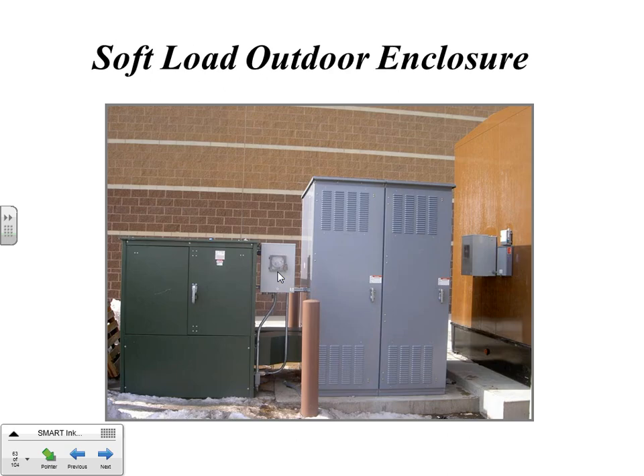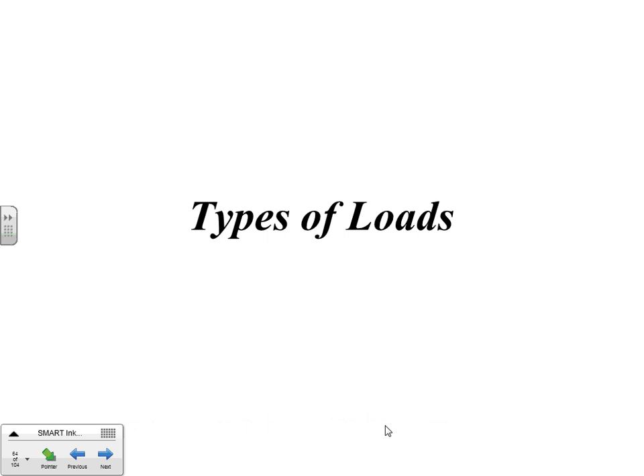This is what it would look like sitting outside of a building. If you remember that super target picture before, it's the same one. The generator has now been set here, and like Chad was saying, here's the utility, here's the generator. We're going to feed them through this device, and the load is connected to the bottom. All right, those are transfer switches.